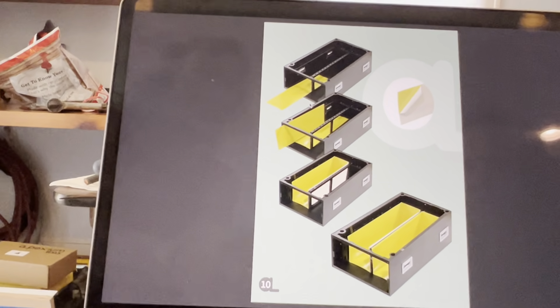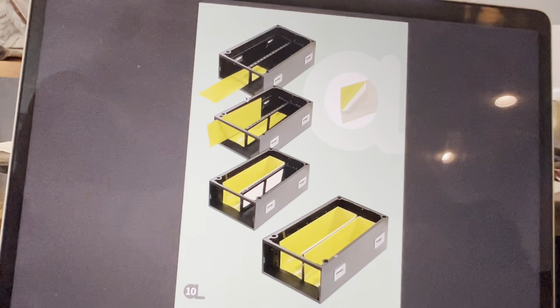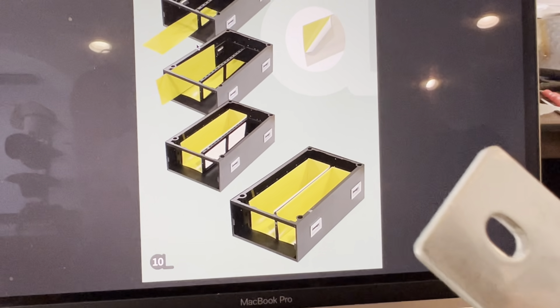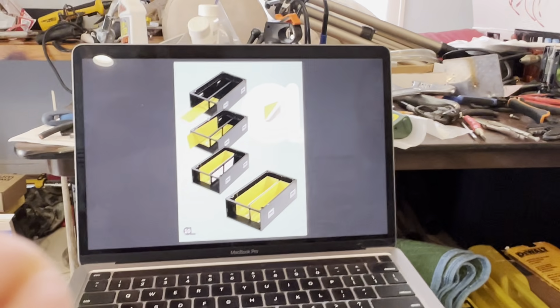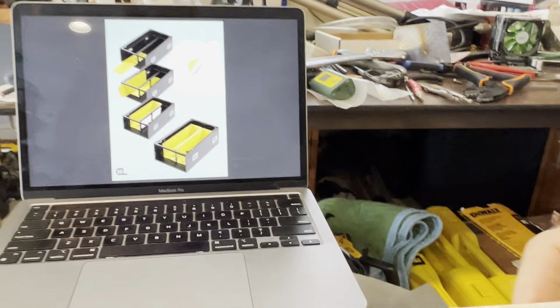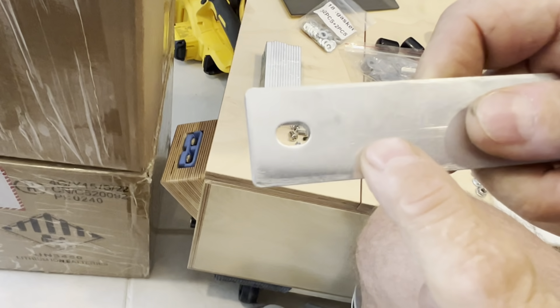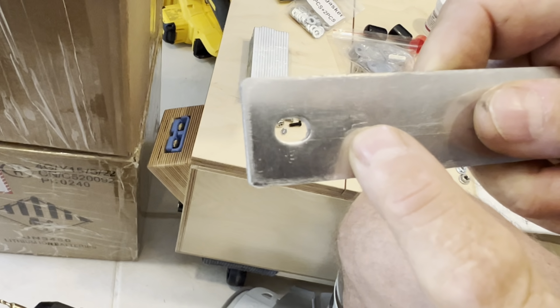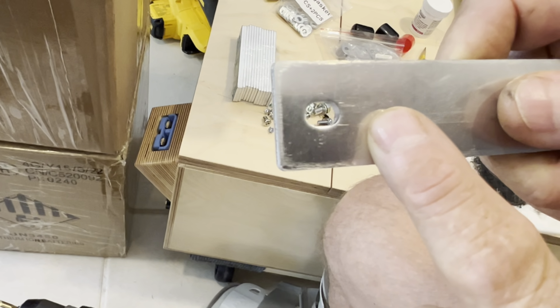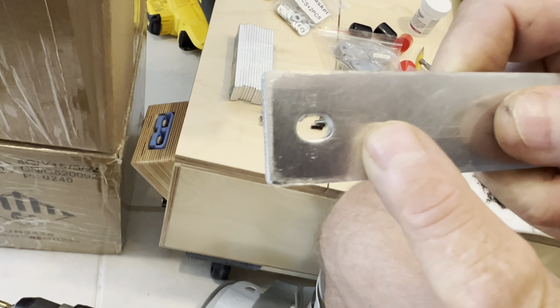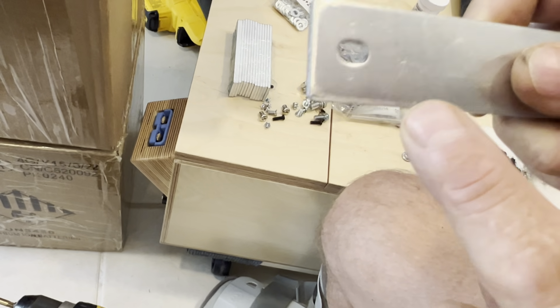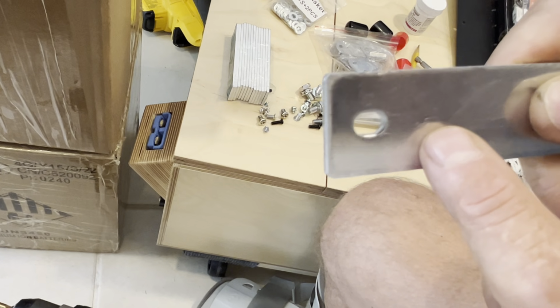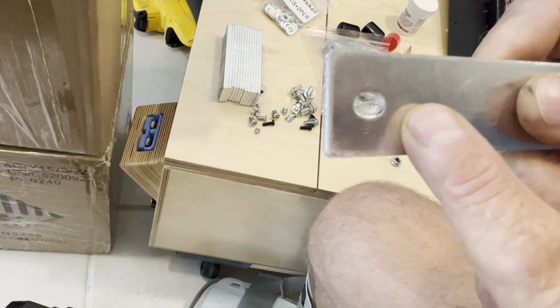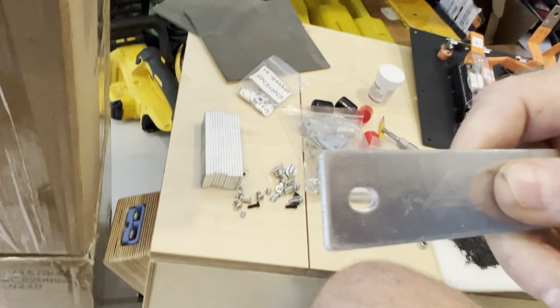I don't trust doing that on an aluminum bus bar. If I tap threads into this aluminum bus bar, I think they will tear out of the aluminum. I have had threaded aluminum tear out the threads many times in the past. And this is fairly thin, so you're only going to get a couple of threads, and I don't think that's a good thing to tap.